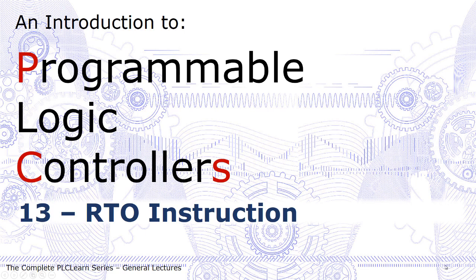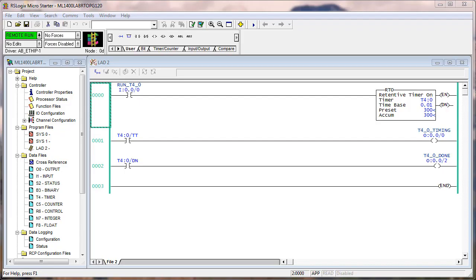The RTO instruction, the retentive on-delay timer instruction. We've already discussed in depth the TON and the TOF, the on-delay timer and the off-delay timer. And I remind you again that there is only one timer data type that's made up of a preset, an accumulate, and then a word with some control bits in it and the time base. This particular processor supports 1 second, 100th of a second, and 1,000th of a second.